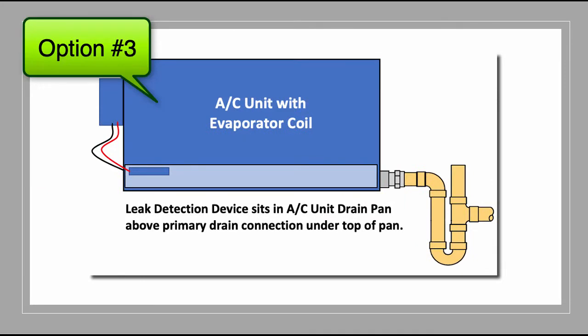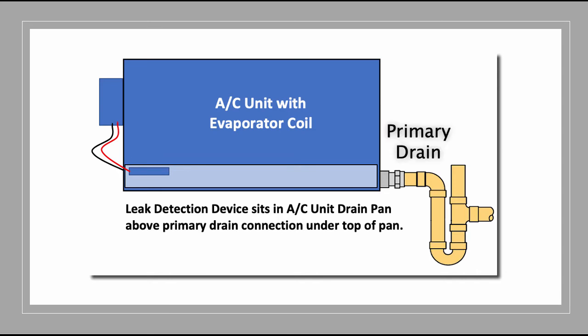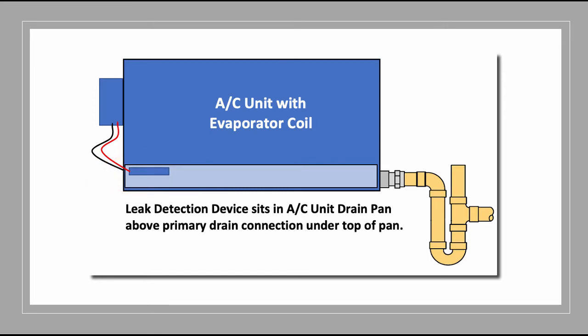Option three: you would use a leak detection device in your drain pan above the location of where the primary drain piping connection is. Once the primary drain clogs, it will start to fill up with water and hit the leak detection device before it reaches the very top of the drain pan. That leak detection device will shut the air conditioner down, preventing water from overflowing the pan.